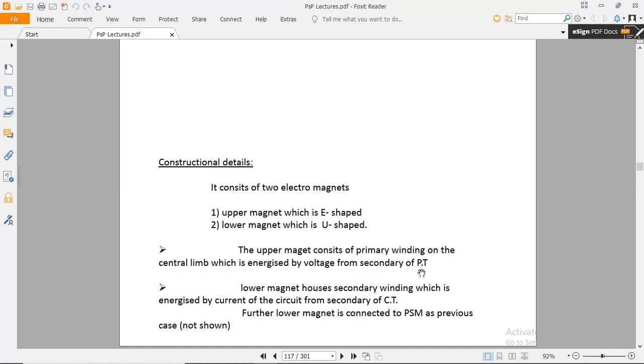The upper magnet of an E shape acts as the central limb, which is energized by voltage from the secondary of the PT, the potential transformer, the set on the upper side. The lower magnet houses the secondary winding, which is energized by the current of the circuit from the secondary of the CT. This is the second set of winding, which provides supply to the U shape. Further, the lower magnet is connected to the PSM as in the previous case, which is not shown.